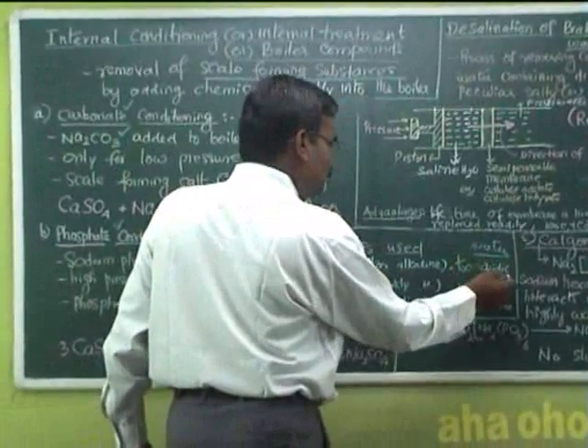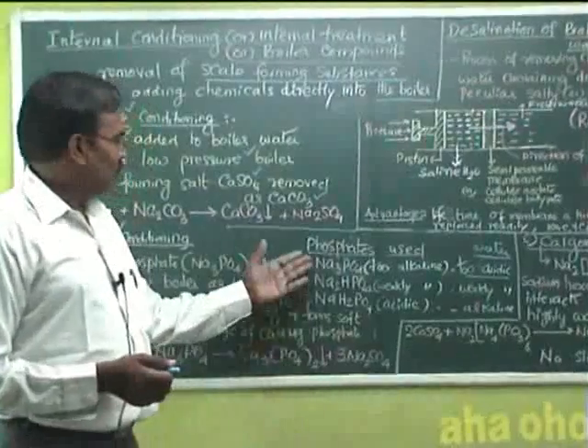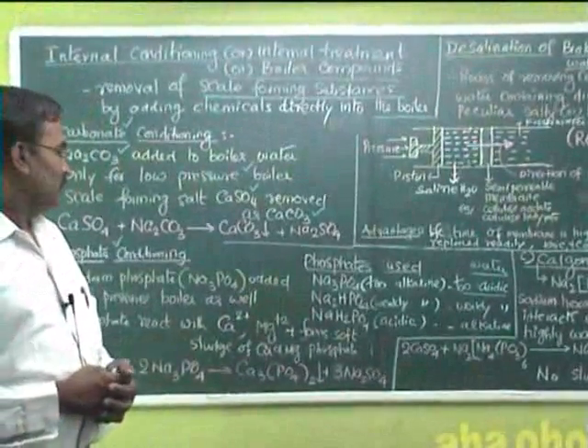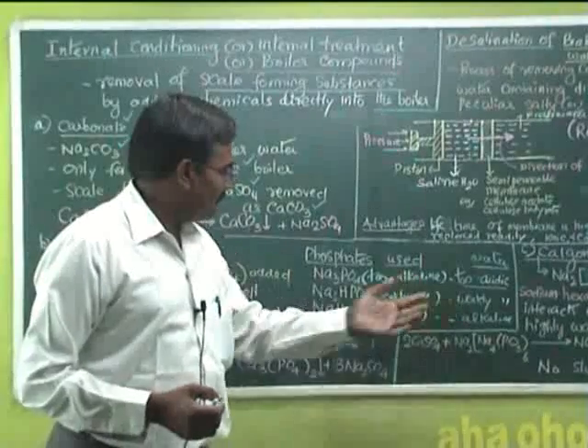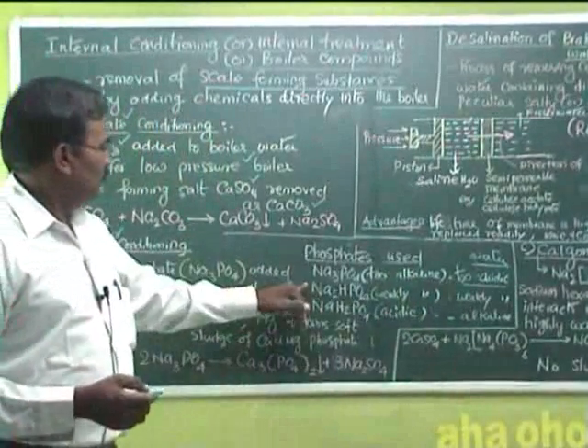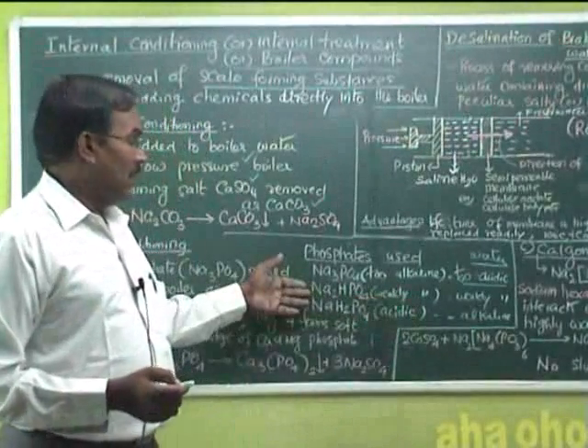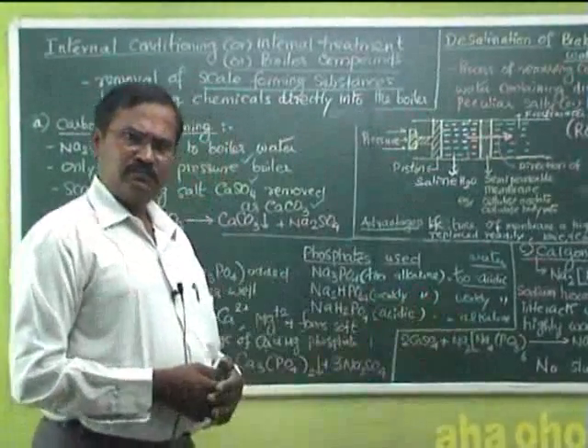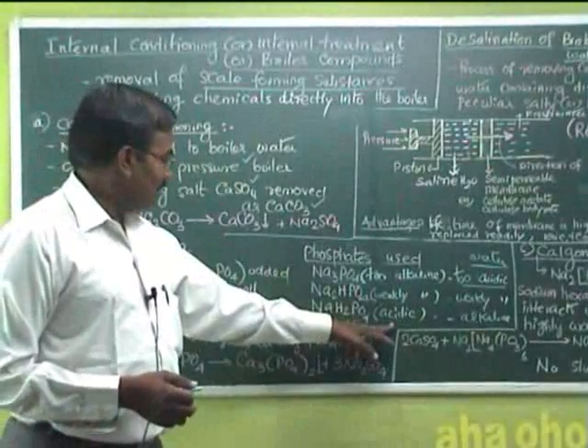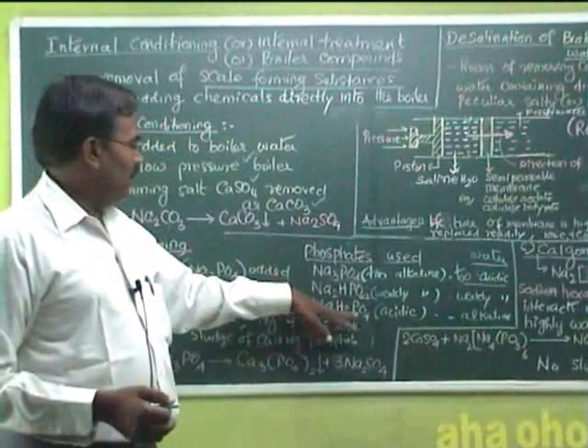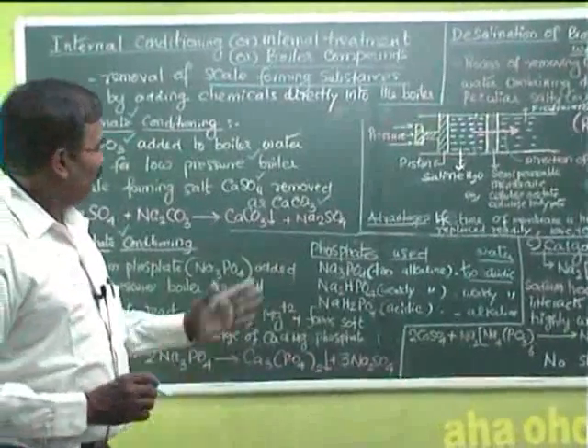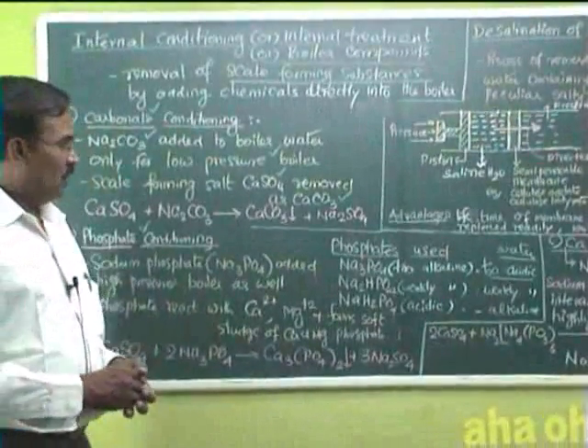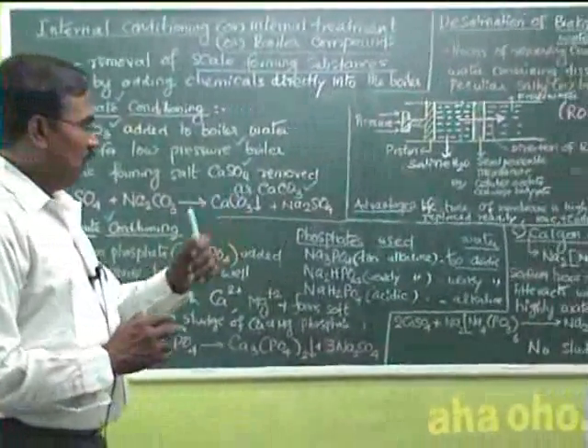Any one of these three can be added according to the nature of the water. If the water is too acidic, we prefer the alkaline phosphate compound sodium phosphate. If the water is weakly acidic, we prefer the weakly alkaline di-sodium hydrogen phosphate. So according to the nature of the water, we can prefer the appropriate phosphate — that is the advantage of this technique.